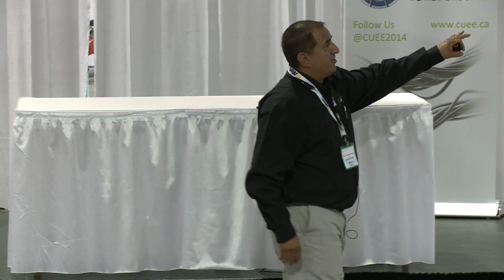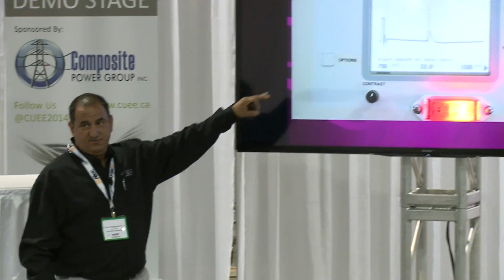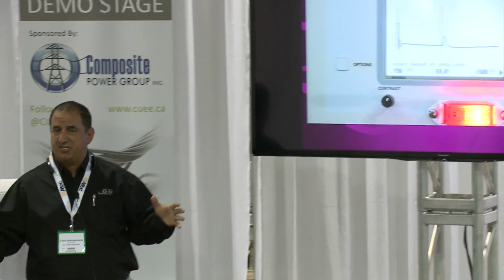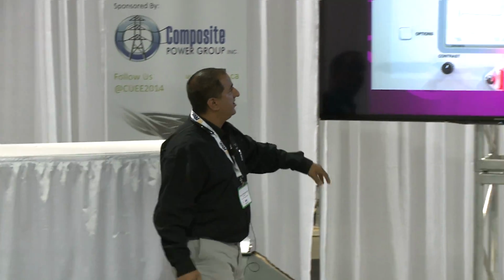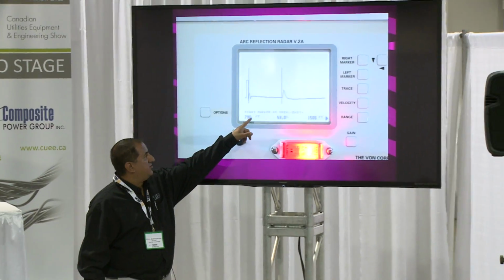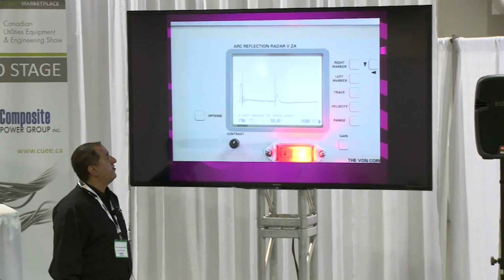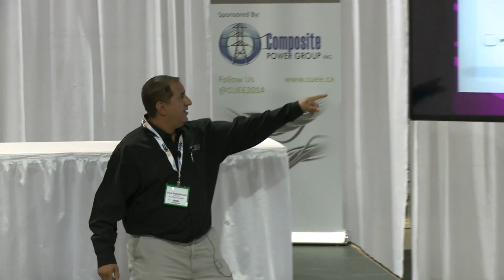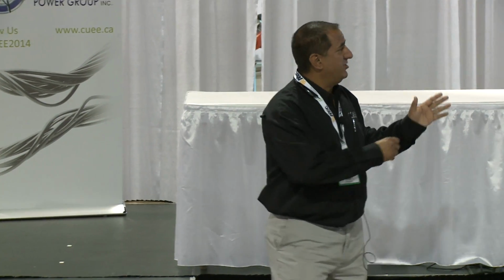So this is a typical, what we would call a radar trace. Once you've made your connection and you've hooked everything up, you're going to turn the machine on. We haven't done anything. Once we do that, we're going to look here. It's always telling us what's happening. Right marker at open or end. And then you see that up spike at about halfway down. That's the end of our cable. So the machine right now is telling us the end of our cable is 796 feet away.